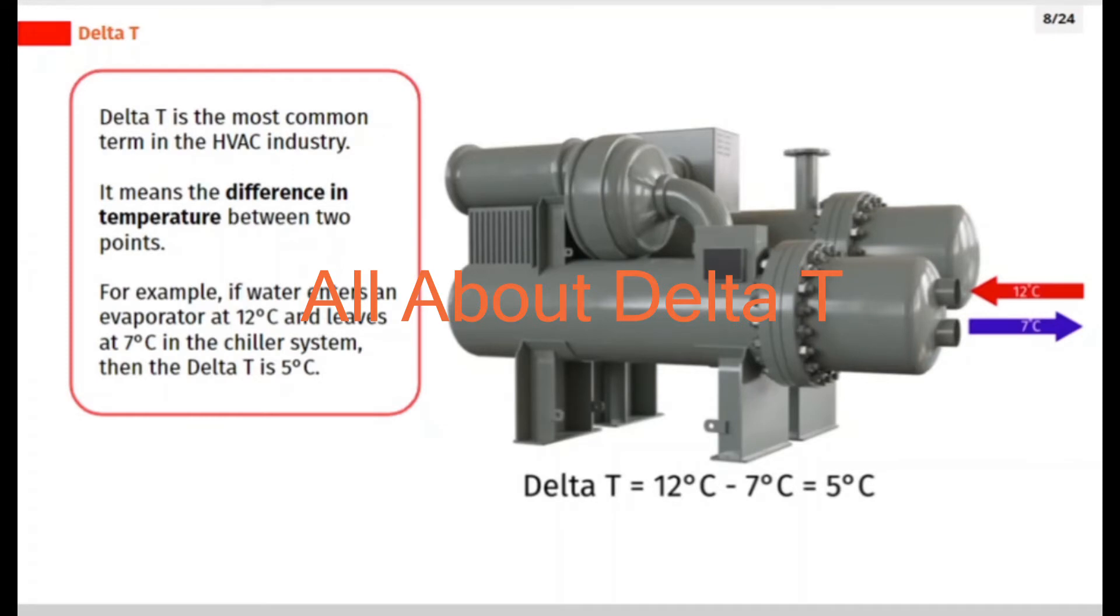Delta T is the most common term in the HVAC industry. It means the difference in temperature between two points. For example, if water enters an evaporator at 12 degrees Celsius and leaves at 7 degrees Celsius in the chiller system, then the delta T is 5 degrees Celsius.